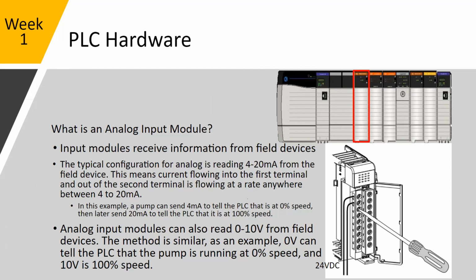4 to 20 milliamps is by far the most common analog input, but there are other examples of them. For the ControlLogix platform, the card can be configured to accept different inputs. Other platforms, you would have to buy very specific cards for these other voltages. So here, for example, you can also read 0 to 10 volts from a field device. The methodology is the same. 0 volts would tell the PLC that the device is at 0%, and 10 volts would be at 100%.